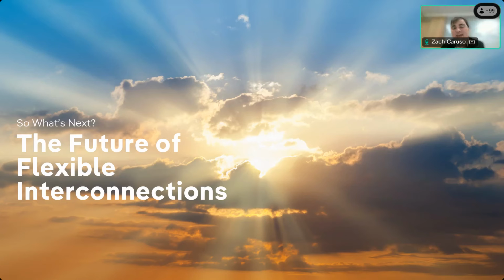And you can, in theory, stack those on top. But at some point, I think you reach the megawatt hour that broke the camel's back, right? At some point there's too much curtailment there to make it feasible. I wouldn't rule out voltage in the long term. It's just right now we're kind of going after low hanging fruit, and that has seemed to be so far thermal constraints primarily at the feeder head and at the substation.